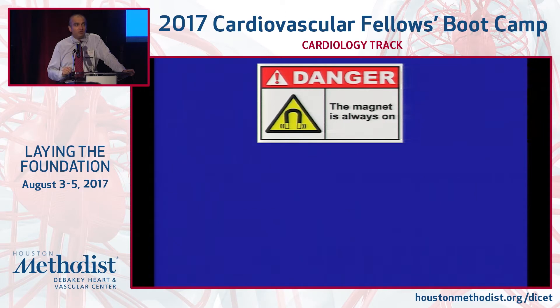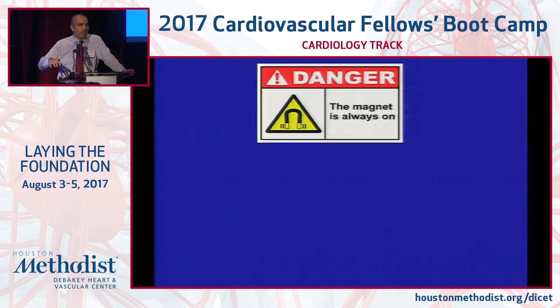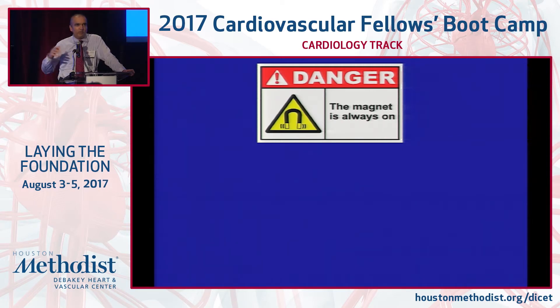Rule number one, rule number two, rule number three: the scanner is a very powerful magnetic field, and that magnet is always on. The lights can be out, it can be the end of the day — it doesn't really matter. That magnet is always on and you need to keep that in mind. You do not walk into the MRI room, even if the patient is coding — you don't go into the room to save the patient. You have to bring the patient out of the room.